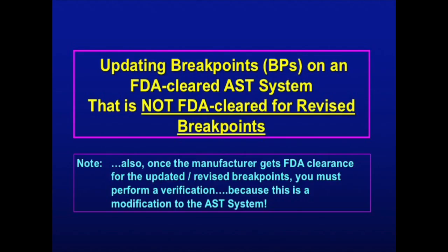Okay, now I'm going to talk about updating the breakpoints on an FDA-cleared AST system that is not FDA cleared for these revised or updated breakpoints. The other thing I want to mention is that manufacturers are now starting to update these breakpoints, and even when those breakpoints are updated, you're going to have to do a verification in that circumstance as well, because it is a modification of the system that you initially verified.